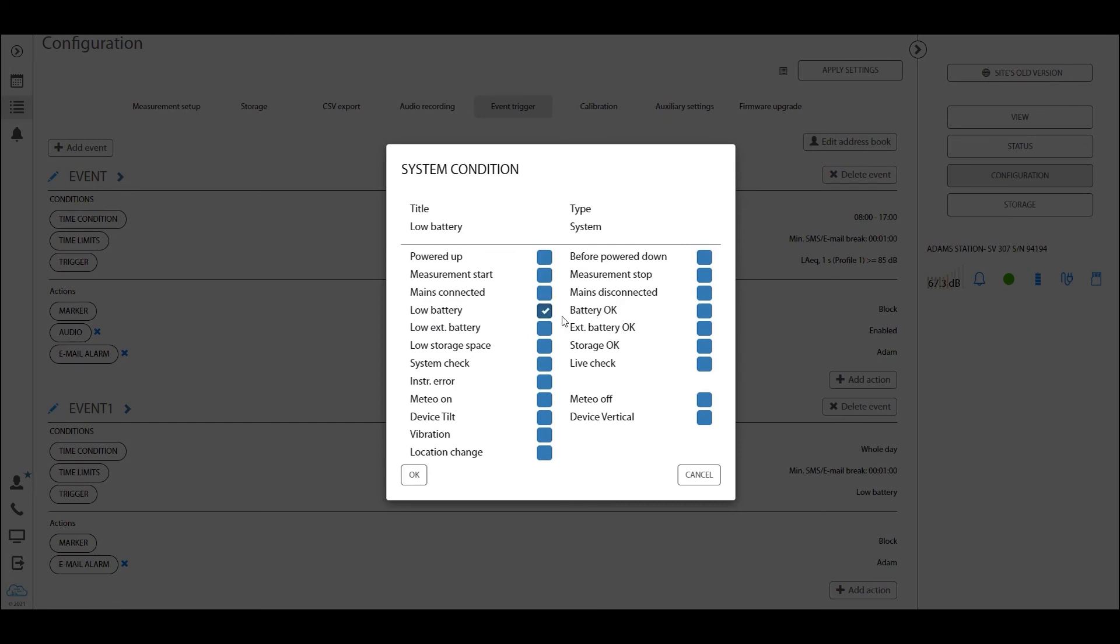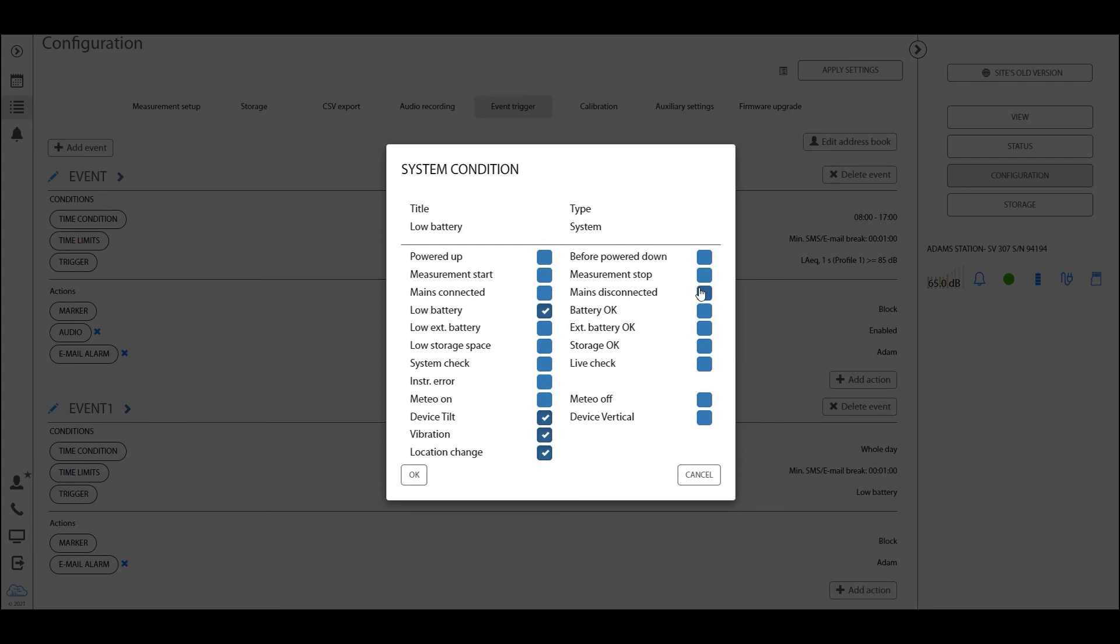And the same way, you are able to add a bunch of other very cool system alarms. For example, device tilt. If the device is more than 45 degrees in decline, so it has gone from its vertical position to a horizontal position, you are able to get an alarm. If there is a high vibration, so somebody bumps the instrument or the instrument fell from its tripod, you can receive an alarm. If location change is registered by the GPS, you can receive an alarm, and so on and so forth. These are very good alarms to have and track on because you can be safe from losing your station.